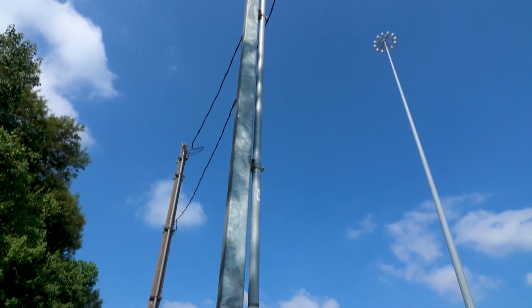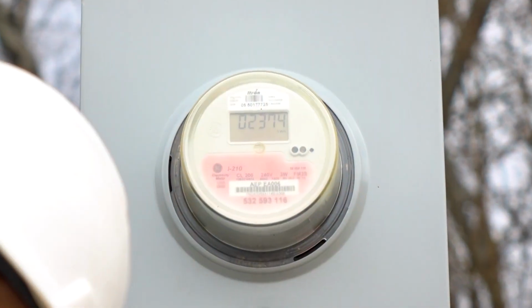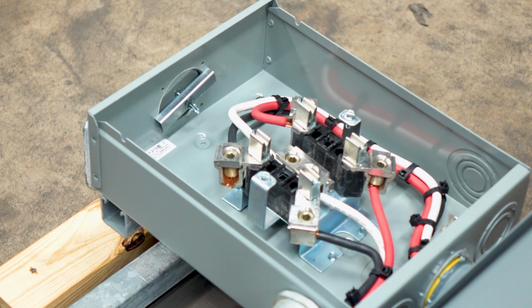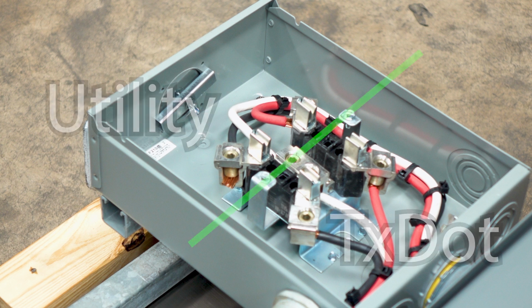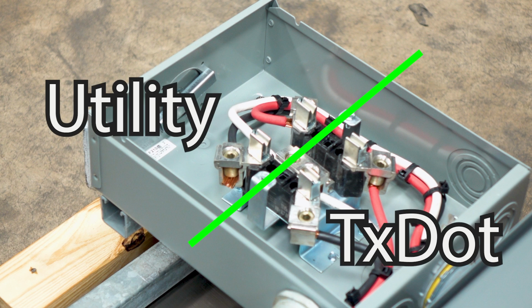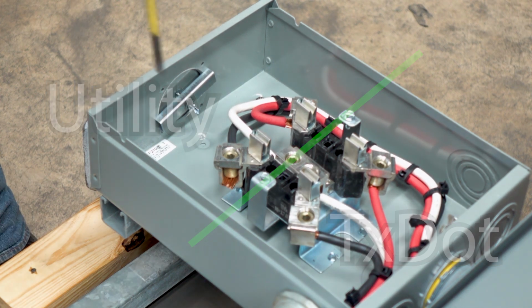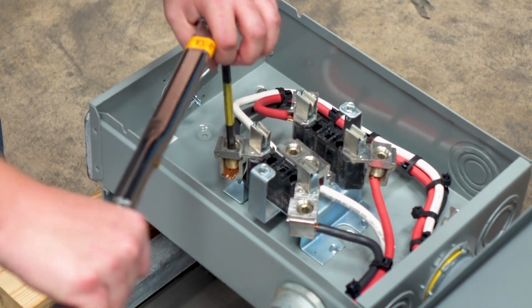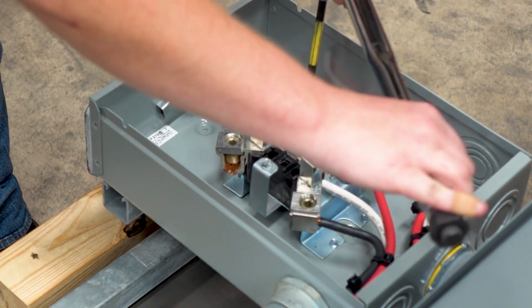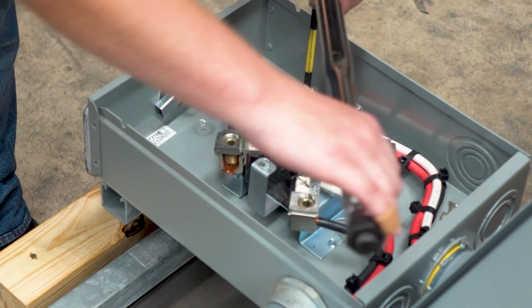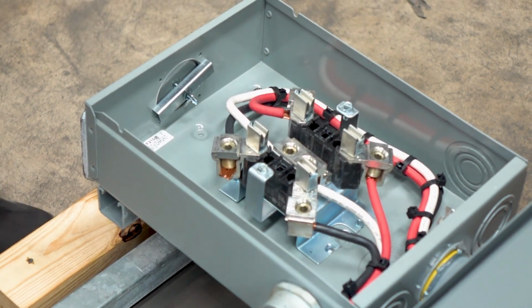The meter socket, or meter base, is installed during the electrical service construction process. The inspector will need to visually confirm that the conductors have been properly terminated and that all the individual strands are inside the electrical lug. The utility company will confirm proper torque of the top 3 conductors. The inspector should confirm that the 3 lower conductors have been properly torqued. This item may not be able to be checked if the meter is already installed. The torque wrench for this inspection task is to be provided and operated by the installing contractor.